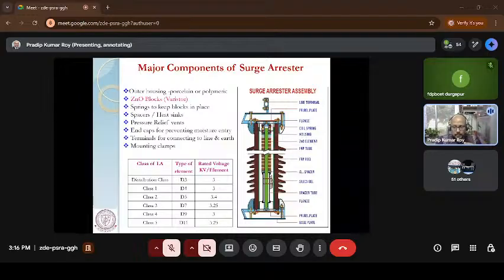Then the blocks are there, and between the blocks there should not be any kind of gap. If any gap is there, there is a chance of flashover through it. So you have to clean, or make the surfaces so parallel, that there is no uneven surface between the top and bottom surfaces. Between these two blocks, there is the aluminum spacer, and if the blocks are filled up and some portion remains, that part is filled up by the aluminum tube.